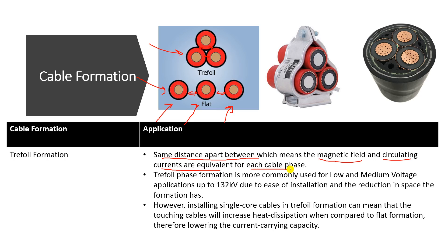This is important for the balance of the three phases — they all suffer from the same conditions. The trefoil formation is commonly used for low voltage and medium voltage up to 132 kV, because it is easy to install and reduces the space required compared to the flat formation, which requires large spaces between cables.